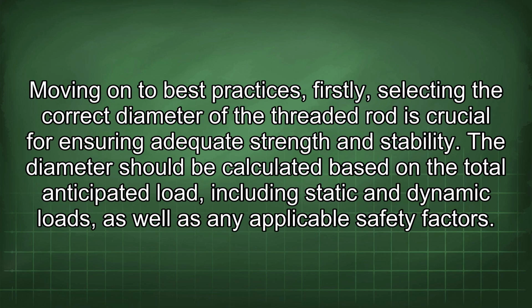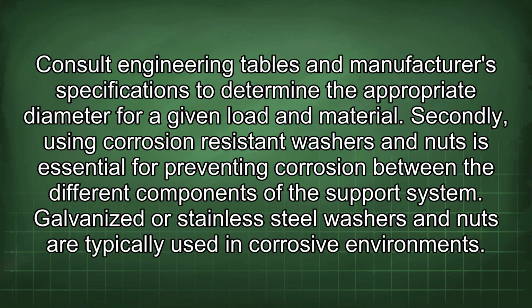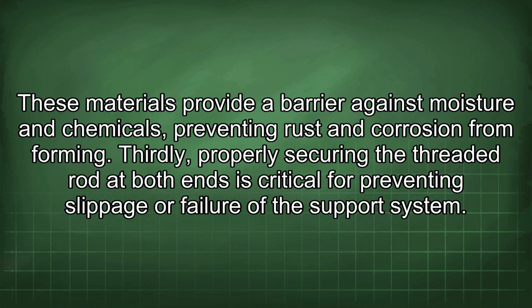Moving on to best practices. Firstly, selecting the correct diameter of the threaded rod is crucial for ensuring adequate strength and stability. The diameter should be calculated based on the total anticipated load, including static and dynamic loads, as well as any applicable safety factors. Consult engineering tables and manufacturer specifications to determine the appropriate diameter for a given load and material. Secondly, using corrosion-resistant washers and nuts is essential for preventing corrosion between the different components of the support system. Galvanized or stainless steel washers and nuts are typically used in corrosive environments. These materials provide a barrier against moisture and chemicals, preventing rust and corrosion from forming.